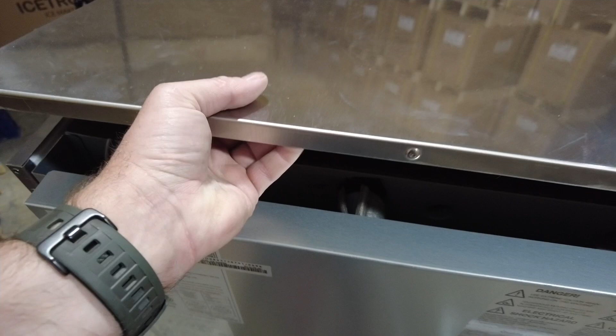You can do it by opening the front cover and accessing the ice thickness probe at that point, but it's a little difficult with that front cover lifted up and back into the machine to access that. So, as long as you've got the machine out and haven't installed it under the counter yet, you just remove those 2 thumb screws, pull back on this lid, and it comes right off.